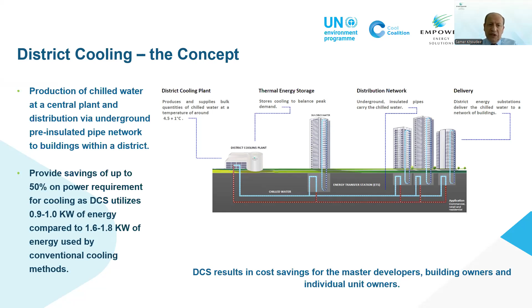In terms of savings, a traditional system runs between 1.6 to 1.8 kilowatts per ton, against the district cooling system at 0.9 to 1 kilowatt per ton. In our area now we're starting to reach less than 0.9 - the latest plant room commissioned is almost 0.85. We're still working with chiller manufacturers to reduce consumption and improve equipment efficiency.